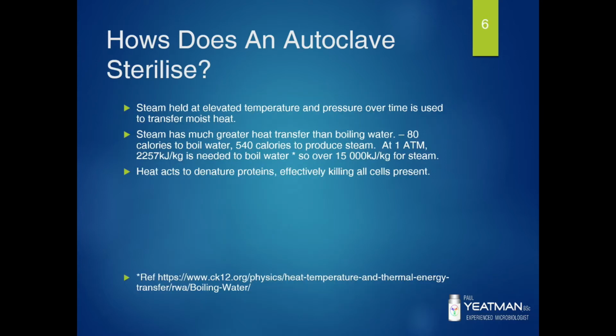How does an autoclave sterilise? So why wouldn't we just use soap or detergent and water to sterilise things? Well, that's only sufficient for sanitisation, which is the reduction of microbes, not the complete eradication of viable organisms. So soap or detergent and water is quite suitable for washing your dishes at home or washing bench tops, because with things you stick in your mouth, if there's low bioload, your stomach acid's going to knock off quite a large number of the microbes, which means that you don't wind up infected. Whereas you'd use an autoclave to totally eradicate any living organisms, because the equipment you're using or the products that you're sterilising can't contain anything living in them. Because if you were to inject, say, a terminally sterilised product into somebody that still had living organisms in it, that could possibly infect the person, give them septicemia, kill them. Now that's the worst case scenario, which you don't want.